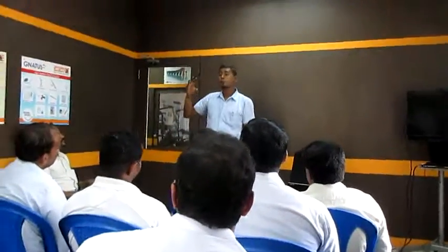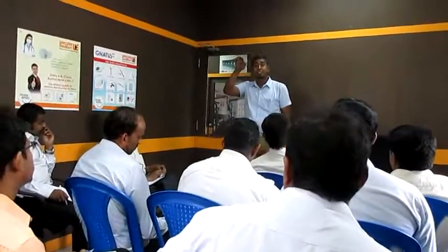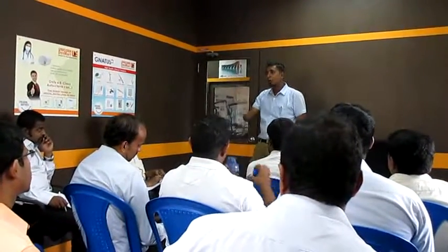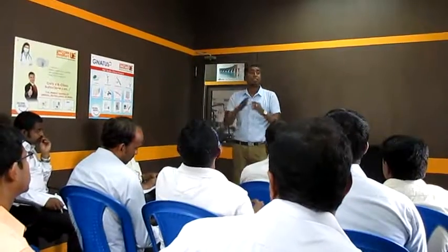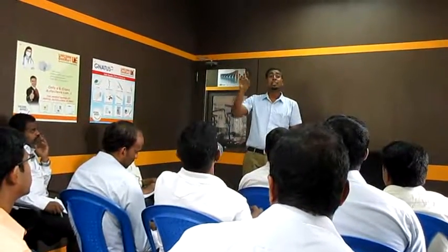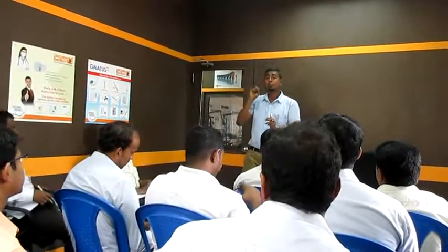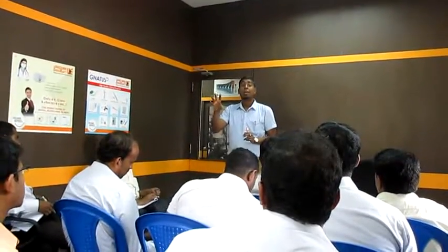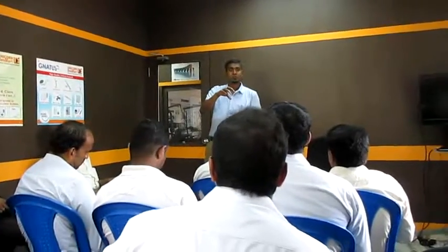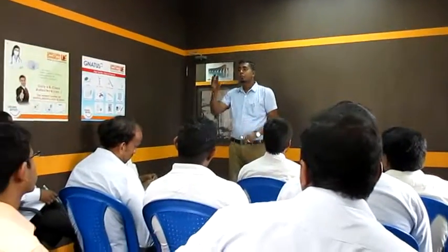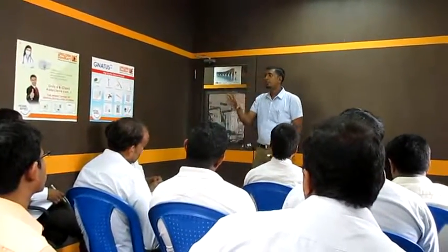Why? Because over a period of time, the machine deteriorates. The kV goes down, the mA goes down, the linearity is finished. So you need to keep your machine on for a longer duration so that it can produce more dose, and more quality dose. So all these 5 parameters change with time.